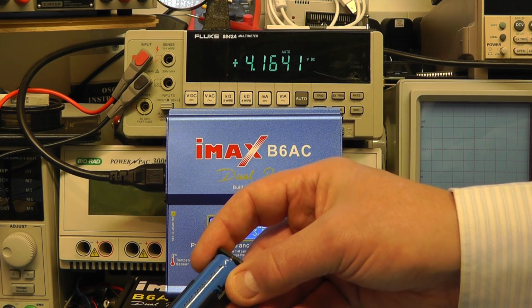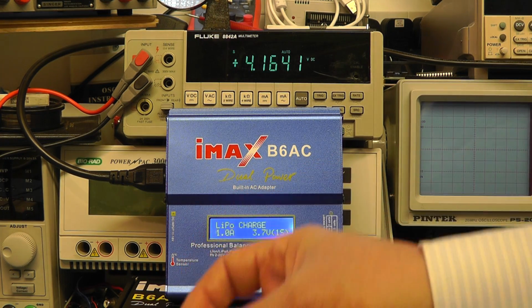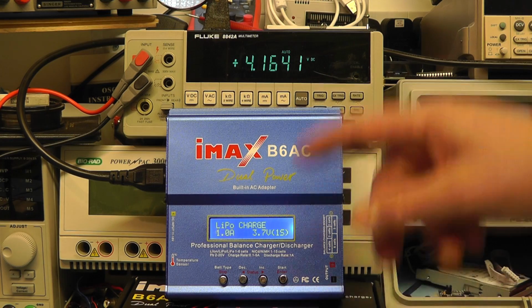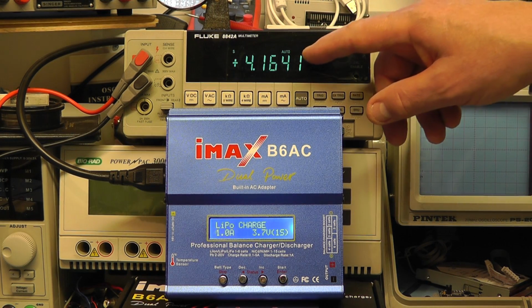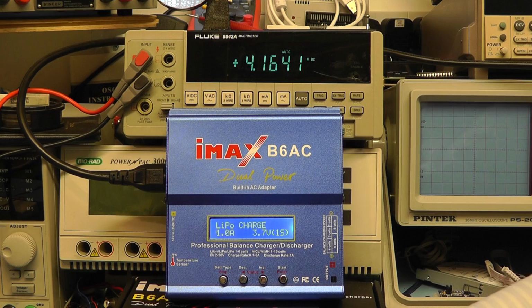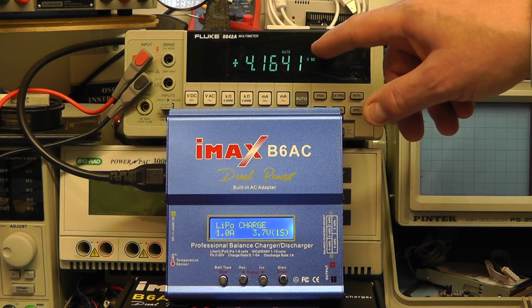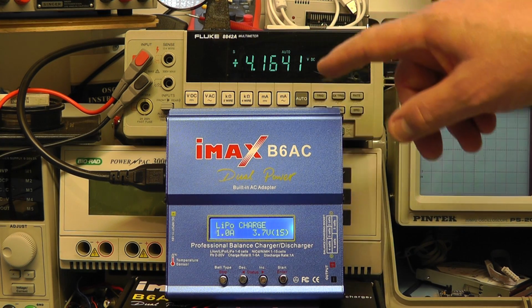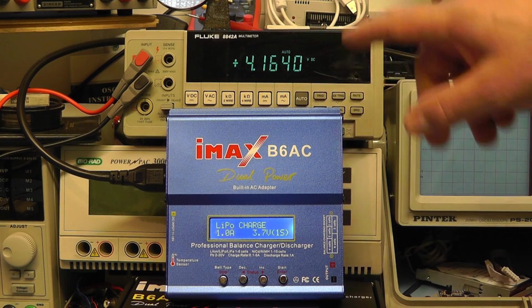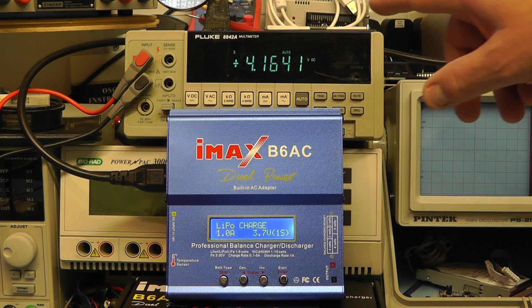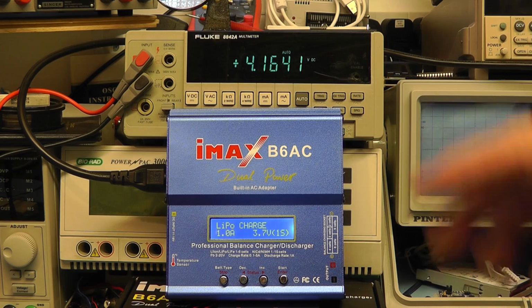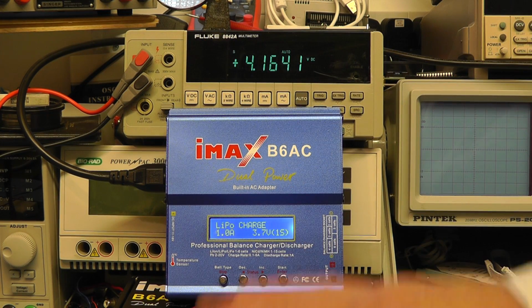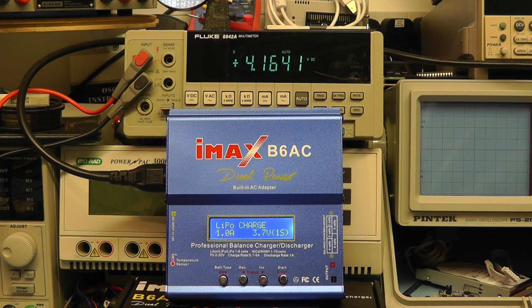Here I'm using a lithium-ion battery, and if you look at the test meter here, that's reading the voltage from that particular battery, which is fully charged, and it's reading 4.164 volts. And I'm going to use that battery to calibrate the unit.